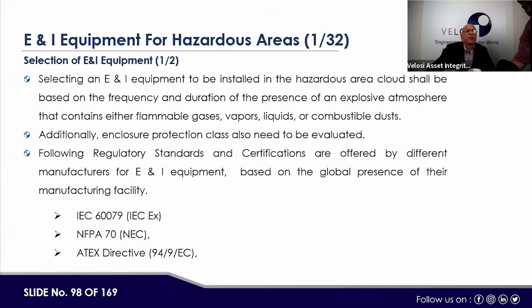Now, the first thing is the selection of E&I equipment in those areas, and the applicable standards. The selection of E&I equipment to be installed in the hazardous area shall be based on the zone classification, the same hazard area classification we have done earlier. Additionally, the enclosure protection class also needs to be evaluated. The standard which I normally follow is IEC 60079, which we call IEC explosion proof equipment. Then NFPA 70, normally called NEC. Then the ATEX directive, or ATEX 94/9/EC. These three terminologies are there.